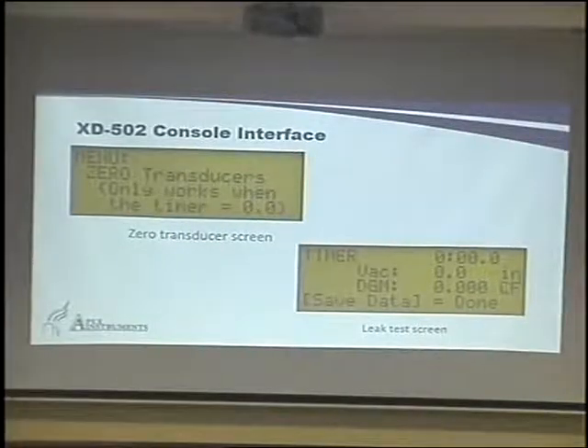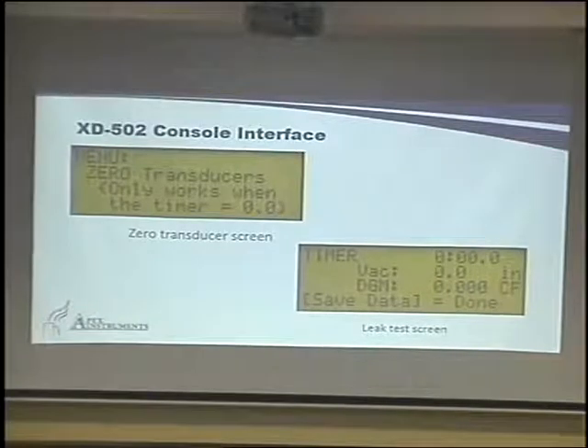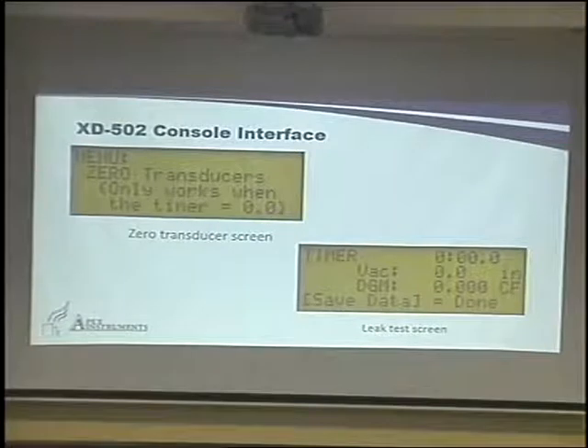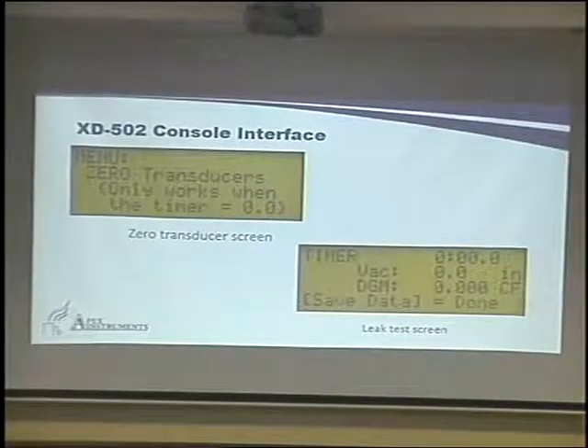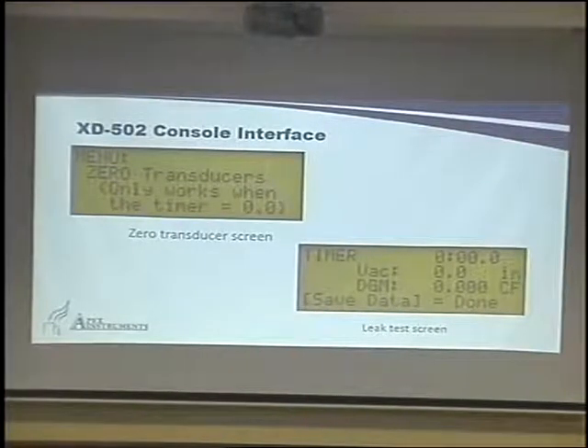Humid temperatures in the truck, and you get it to site and you take it up and you turn it on. Now those pressure transducers might have drifted a little bit. They're reading a positive or negative number with no flow coming through them. We can quickly zero those pressure transducers. Basically what we do is we take the calibration curve and we move it slightly back to zero.